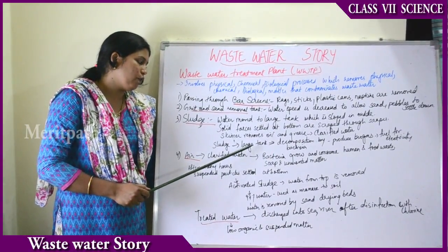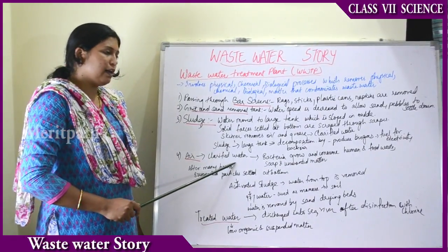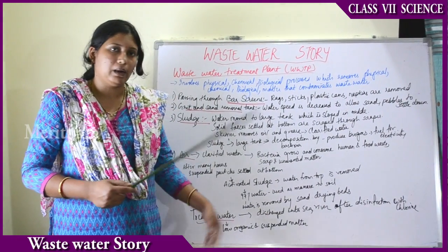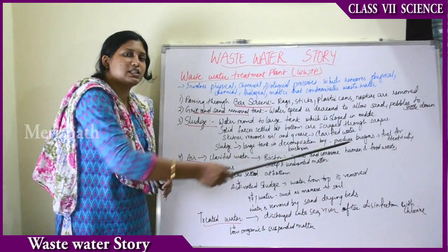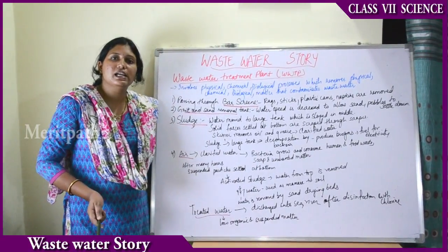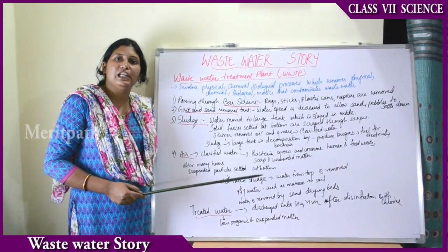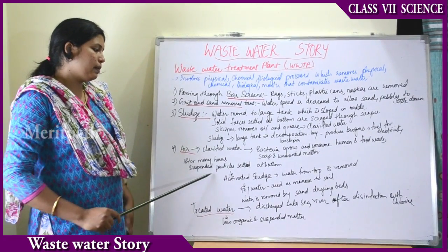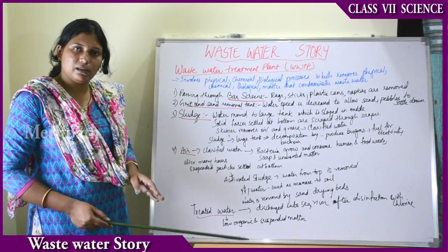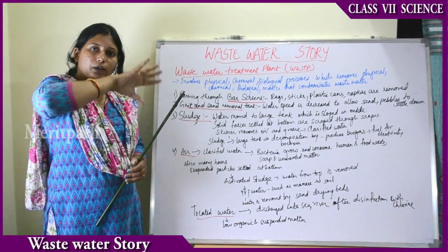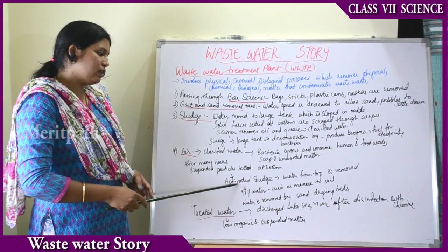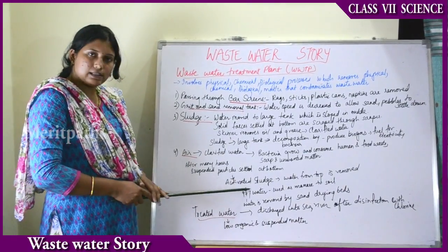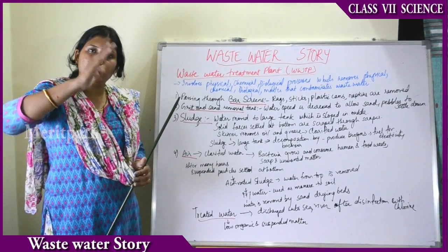From the clarified water, air is passed through it. This air helps the bacteria from the sludge to grow and multiply. The bacteria eat the human waste, food waste, soap, and unwanted materials present in the water. After many hours, the suspended particles settle at the bottom, and the water floats at the top. The top water is removed, and the remaining settled particles are known as activated sludge.